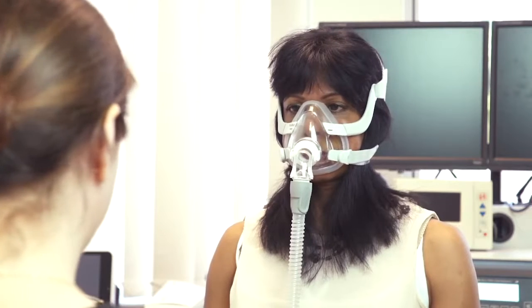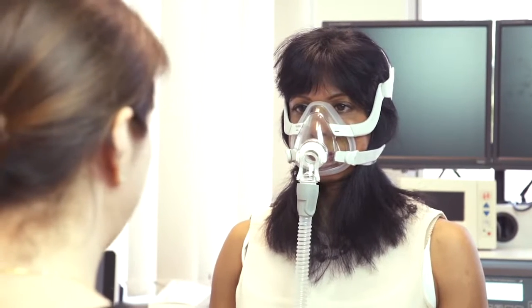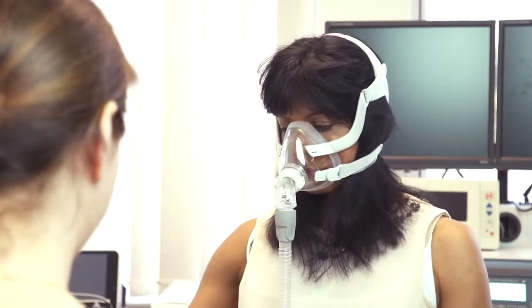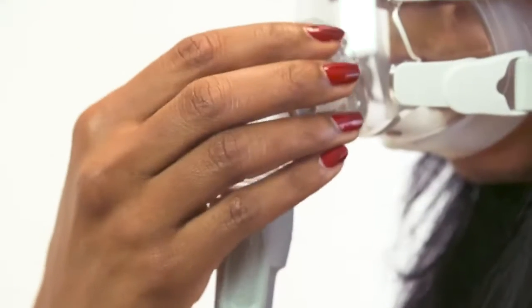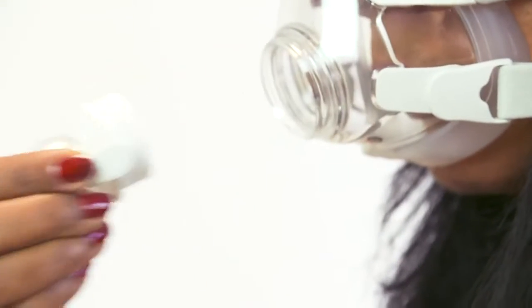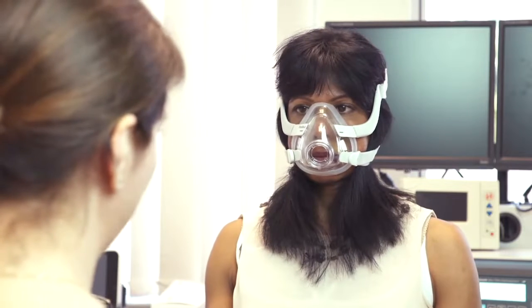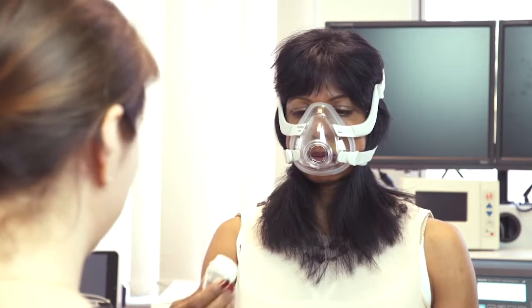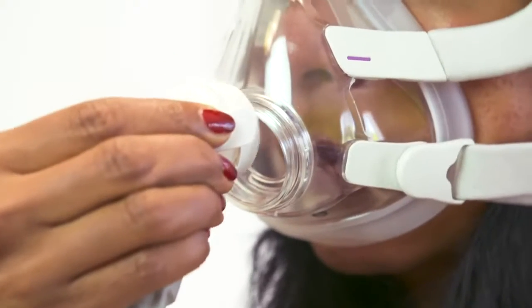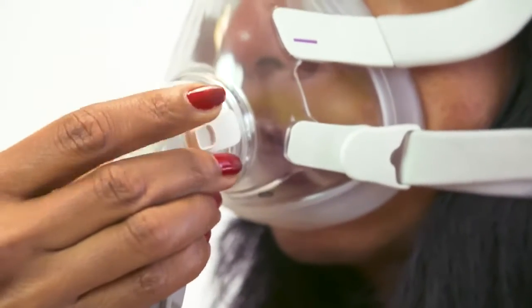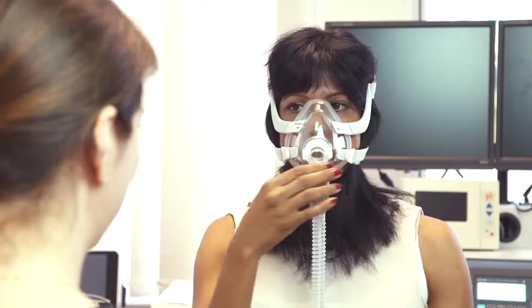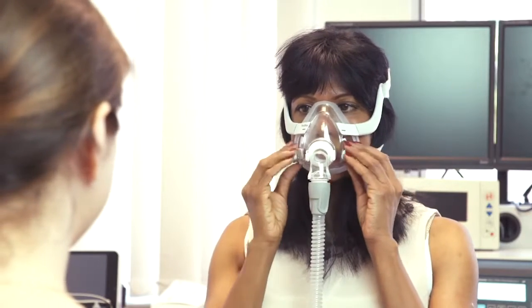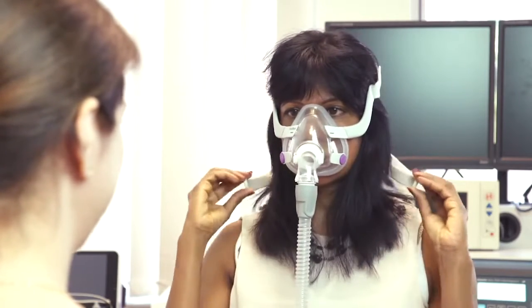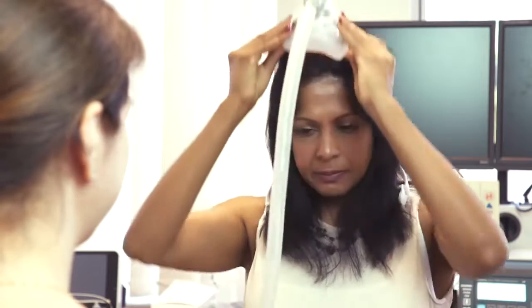If you need to wake up and go to the loo during the night or have a sip of water, you can detach yourself from the elbow joint. So if you turn the machine off, pinch the two clips on either side of the elbow joint and release yourself from there. If you have a straw, you could have a sip of water through that opening there. Once you've had your sip of water or come back from the bathroom, you then reattach the elbow joint. Make sure it's secure. If I want to take it off this way, I can also do this, can't I? Yes, and lift it over your head.